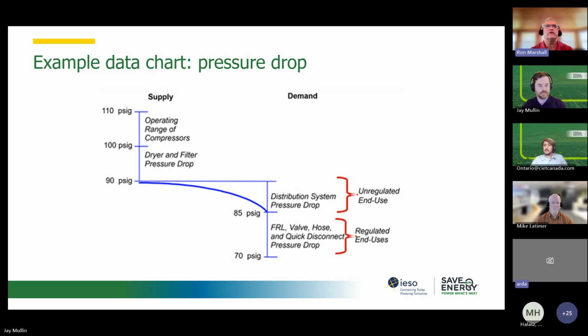So for a few $100s, we can fix that problem at the end use, right, and get better pressure. A few $1,000s, we might be able to loop the piping and get rid of some of that distribution pressure drop or increase the size. And multi-thousands might have to be spent to upsize the dryer, do better filtering, right, to address the problem in the compressor room.